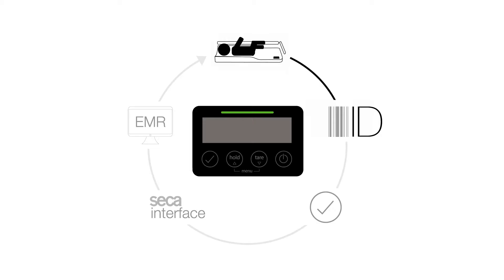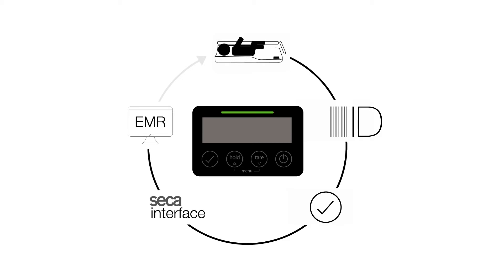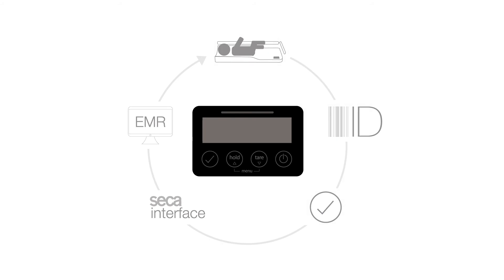That concludes the measurement and approves the measurement data to be sent to the EMR. During the transmission of the data to the EMR, the LED above the display flashes to indicate the transmission. When the data arrives in the patient's EMR, the LED stops blinking and remains lit for another 5 seconds. After that time, the LED turns off and a new measurement can begin.